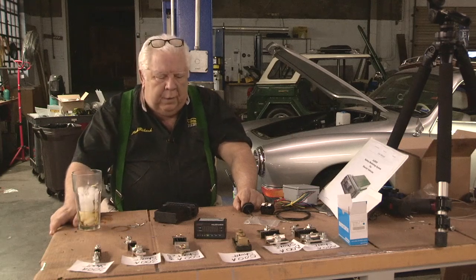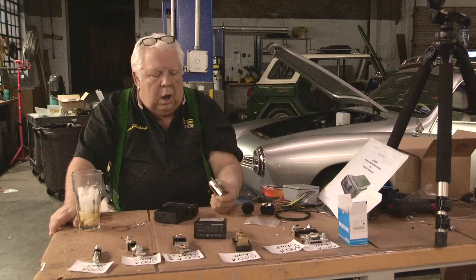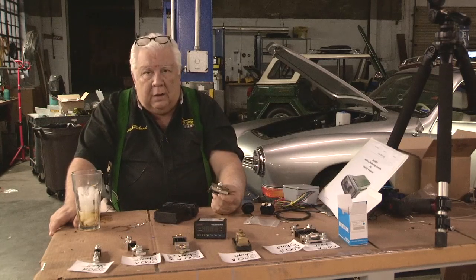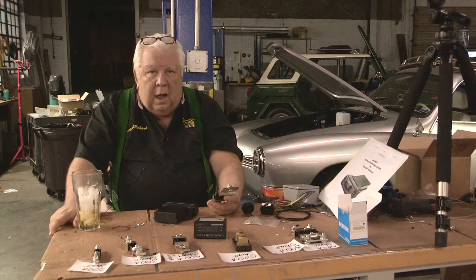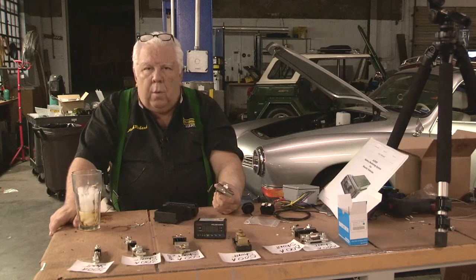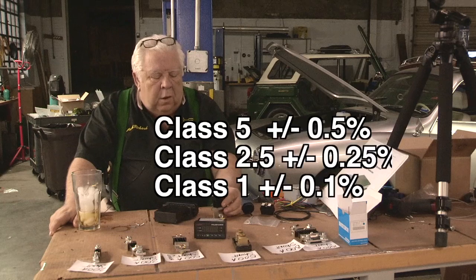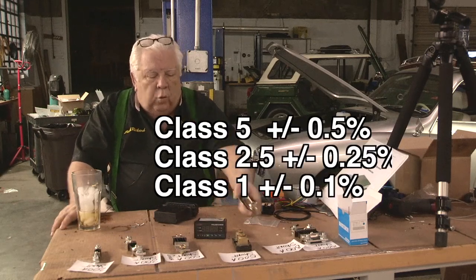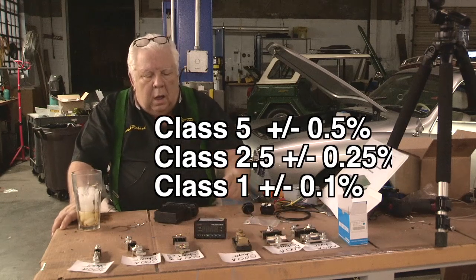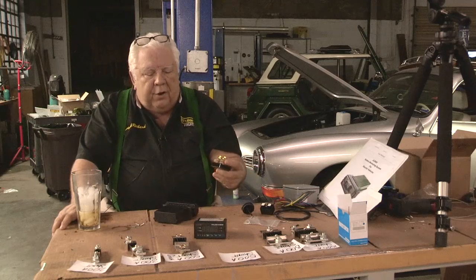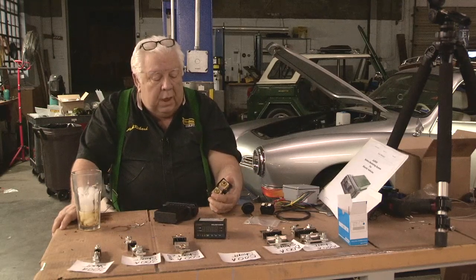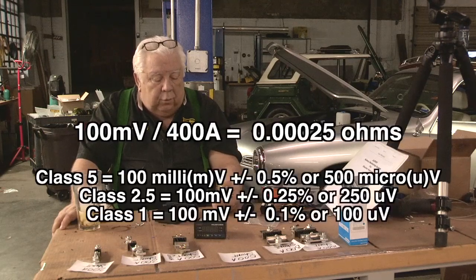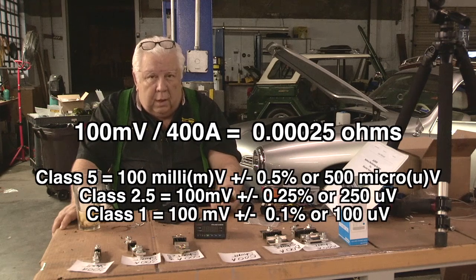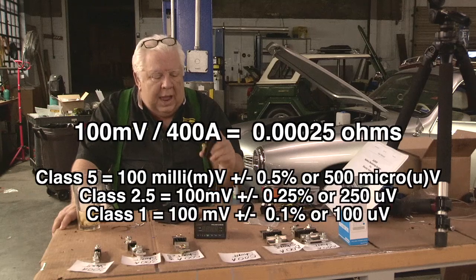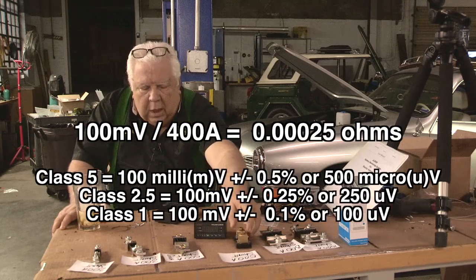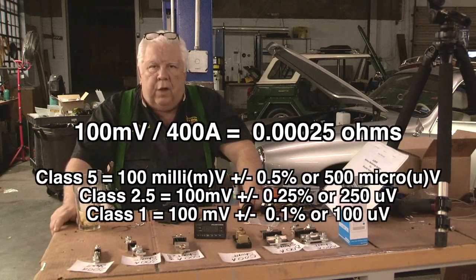Let's talk about accuracy. These Chinese shunts are what they call a Class 5. Class 5 means actually that it is good plus or minus 0.5%. The resistance on this shunt will be within 1/2 of 1% of what's advertised. This 50 millivolt 500 amp happens to be a Class 2.5, and that is another commonly available shunt, and that will give you 0.25 or 1/4% accuracy on your resistance. There are lower ones, and the price goes up as you go down.